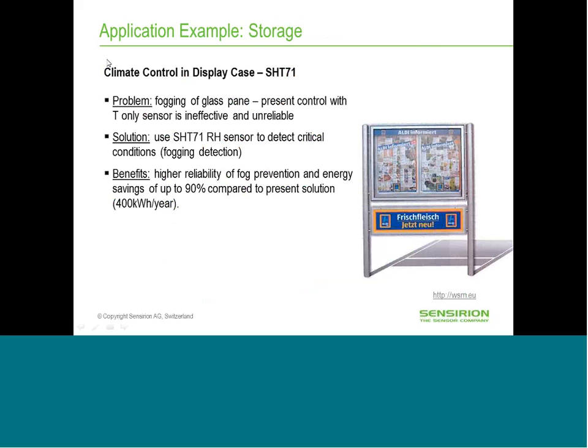It's the use of an SHT71 in a display case, in this case for a supermarket. These cases have the problem that sometimes the glass fogs up, so you have condensation of water on the glass. Currently, this is solved by using a temperature sensor and controlling a heater based on temperature information alone. But this control is very ineffective and unreliable, because with a temperature sensor alone you cannot detect the critical conditions.